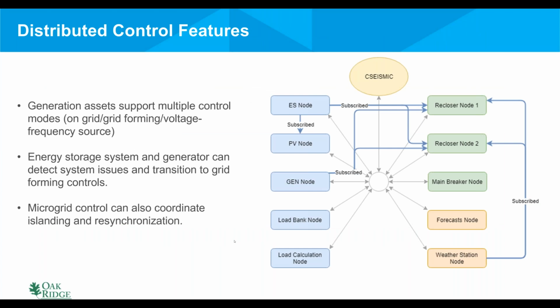So with all of that in mind, the different aspects of controls that one needs to be cognizant of, the program that we use to control the microgrid is called SEISMIC, and it takes into consideration all of those aspects. SEISMIC is an open source program being further developed by Oak Ridge National Lab. And what SEISMIC is tasked to do is to ensure that the generation assets in the microgrid can support multiple control modes while on grid, and while in island mode, it has to be able to form the grid, regulating the voltage and frequency. And furthermore, SEISMIC has to ensure that the energy storage system and generator can detect system issues and transition to grid forming controls seamlessly. And finally, the microgrid control can also coordinate islanding and resynchronization.